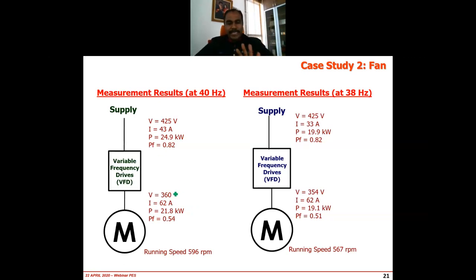Now, what we did was, yes, this particular motor was already connected to a variable frequency drive, and we did something. All the while they were running at 40 hertz. Okay, this again happens in industry. They already installed a VFD, and then they probably already preset a certain frequency. And when we go and ask the technicians and engineers, okay, why 40 hertz? They said it's already preset. They are not allowed to change it. But it's not true, okay?